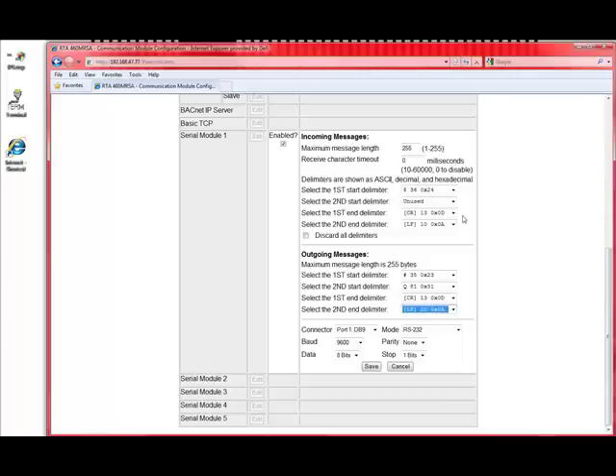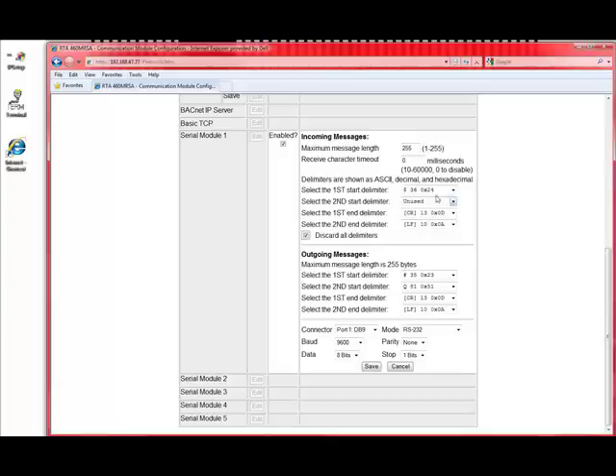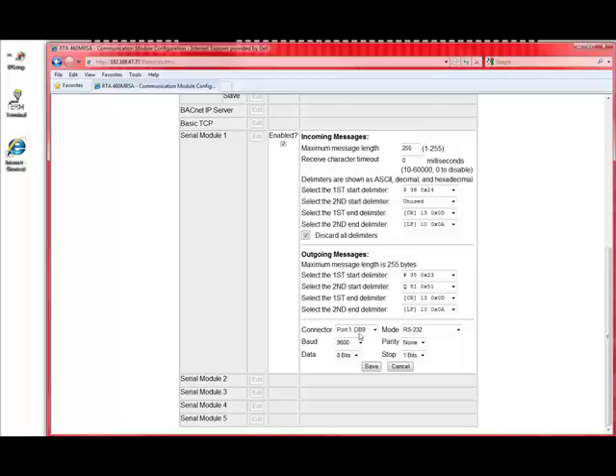Same thing on the input. If we got dollar sign space, ABC, carriage return line feed, I'm going to check discard all delimiters. So, we would get rid of the dollar sign, we would get rid of the carriage return, get rid of the line feed, and we would just send ABC in the message back to the serial mod, to the Modbus module.